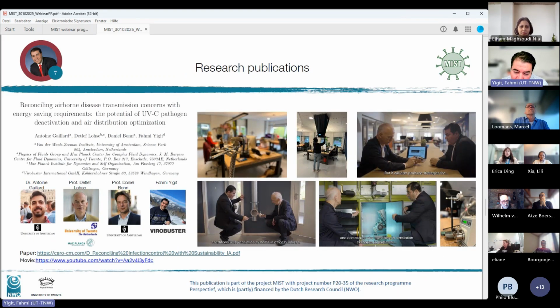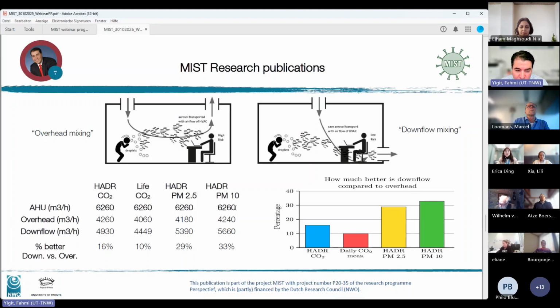Every two weeks we changed the mode of this office, which was occupied by 36 employees, a big open plan office. What was the result? We saw that for the air handling unit itself, measuring literally 6,000 cubic meters, there was a difference between the overhead mixing and the downflow mixing of around 16%.